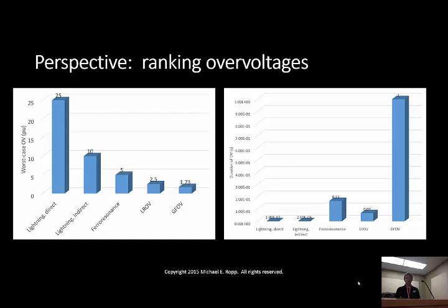So when we design for those, typically arresters are designed to handle these big pops, but for relatively short periods of time. The middle one there that goes up to 5 per unit, that is a ferroresonant condition.